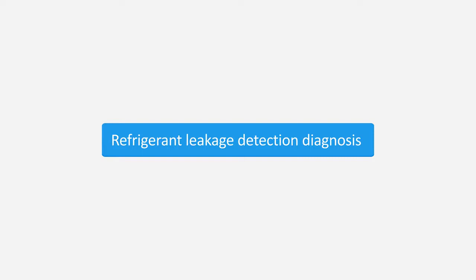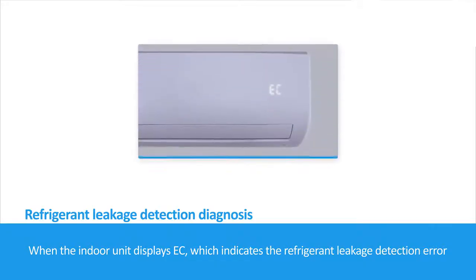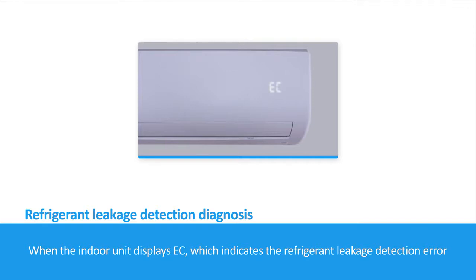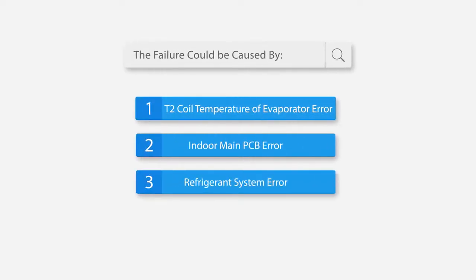Refrigerant Leakage Detection Diagnosis. When the indoor unit displays EC, which indicates the Refrigerant Leakage Detection Error, the failure could be caused by: 1. T2 Coil Temperature of Evaporator Error, 2. Indoor Main PCB Error, 3. Refrigerant System Error.